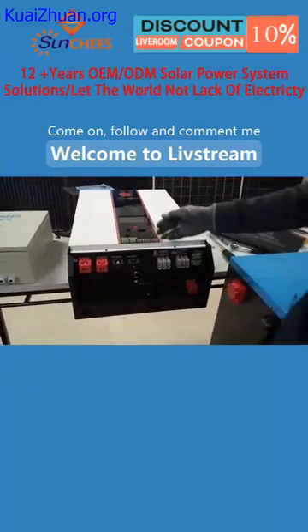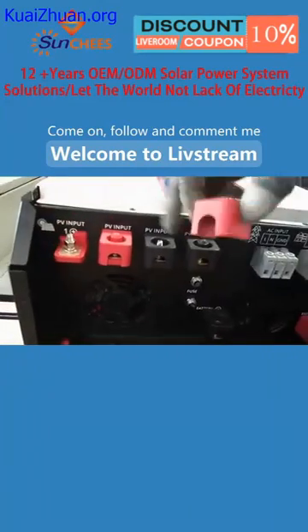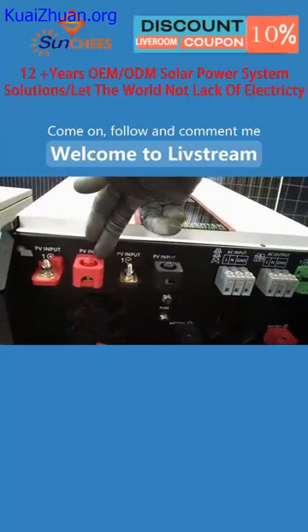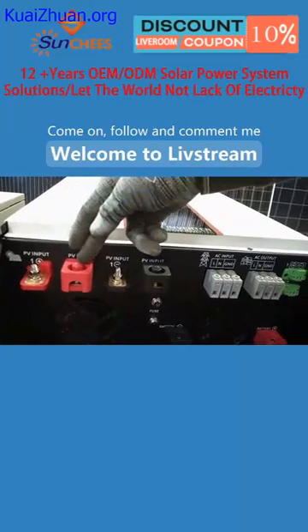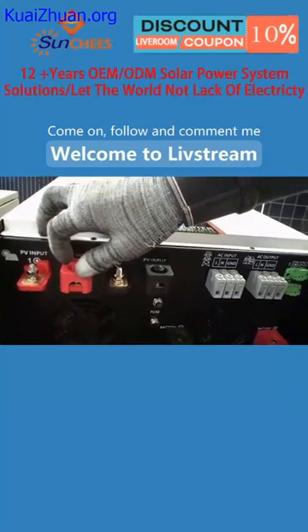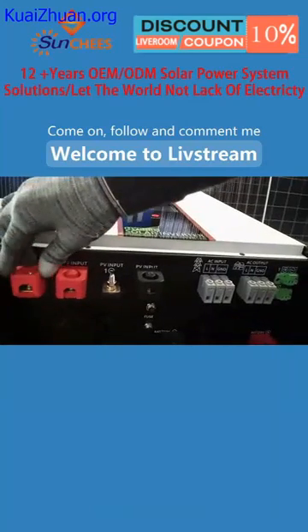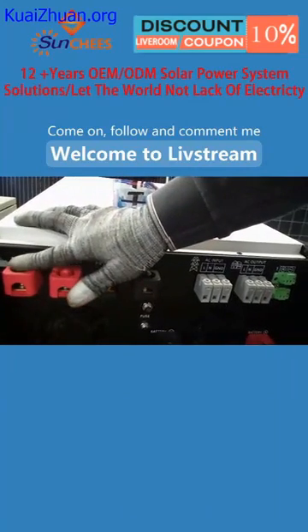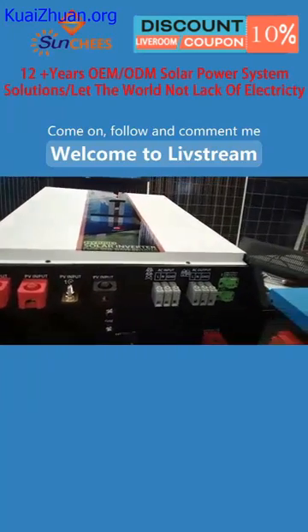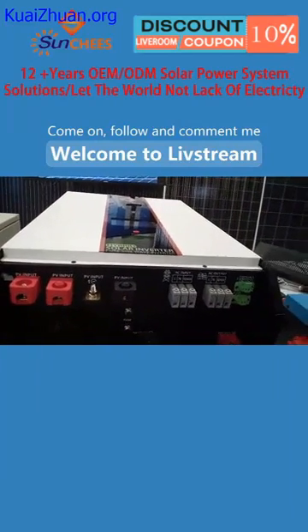You can see for the hybrid inverter, we have 2 sets of input ports. One is PV1, PV2. Each one is 60 ampere. So the hybrid inverter uses 2 pieces of 60 ampere Mppt charge controller working in parallel to make the complete set Mppt charging current reach 120 ampere. Our Mppt charging efficiency is up to 99%.